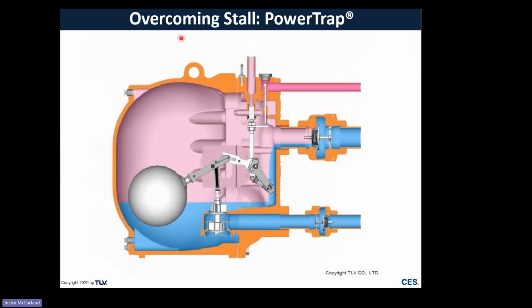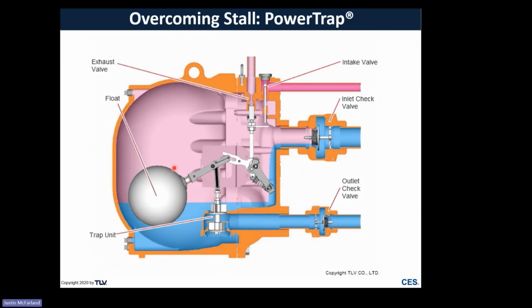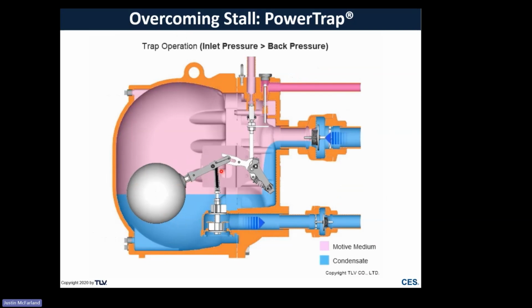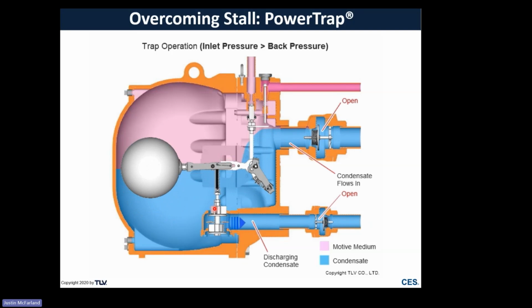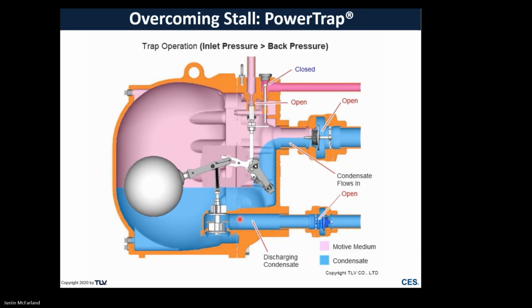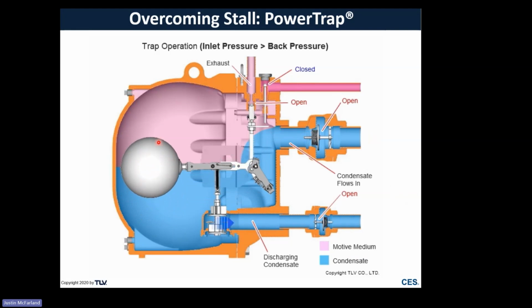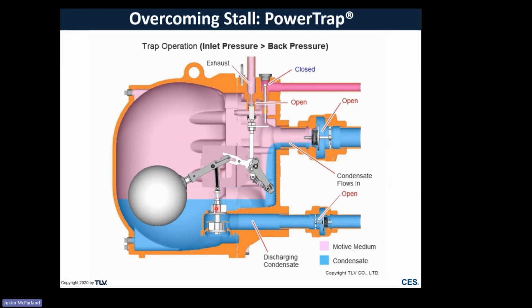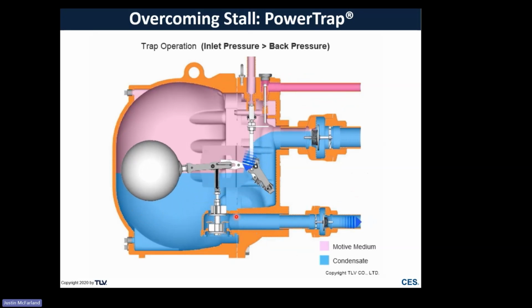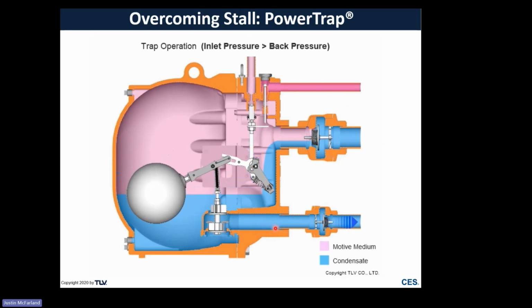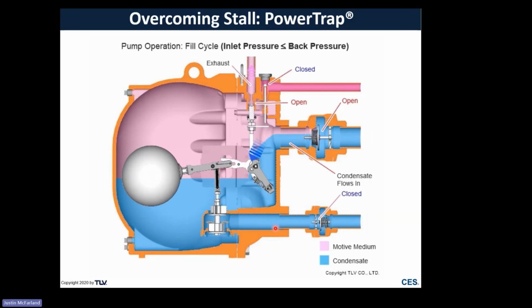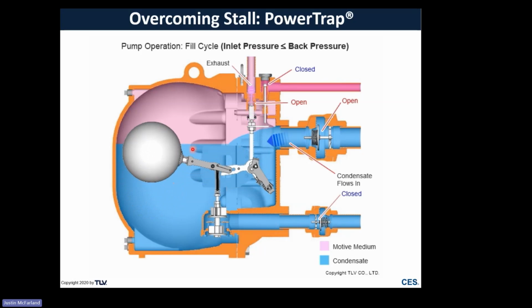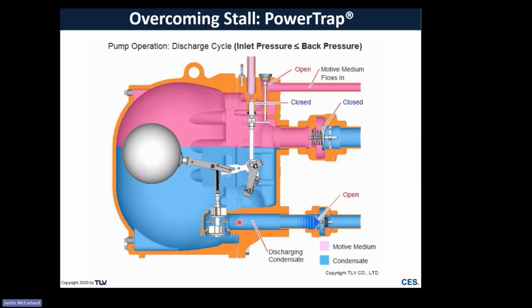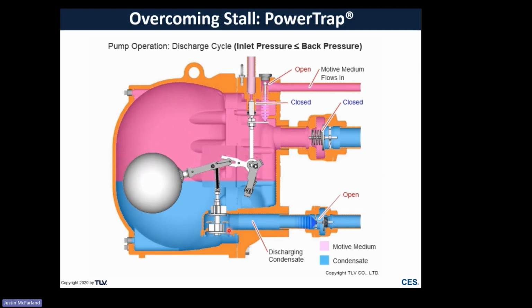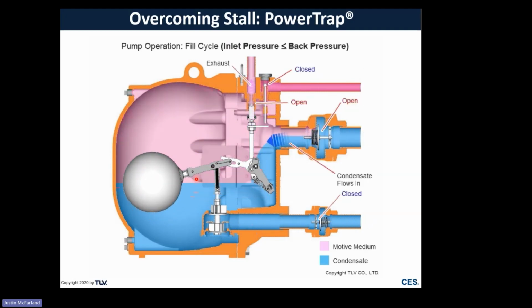So taking a closer look inside, we've got a check valve, an outlet check valve. This is basically a lever float type device where we've got a linkage here. It's tied to a double-seated trap where if we have positive differential pressure, then this float's going to lift up and it's going to push down this plunger, effectively exposing more area for condensate to pass through. And it's going to act just like a steam trap. And if we have negative differential pressure, condensate's going to continue to fill because no matter how much this trap opens up, we don't have positive pressure. Condensate's not flowing. It's going to continue to back up as we see right now.